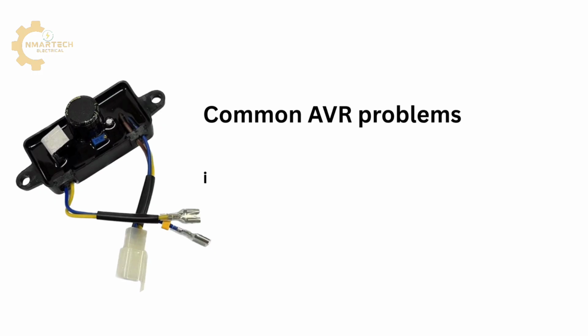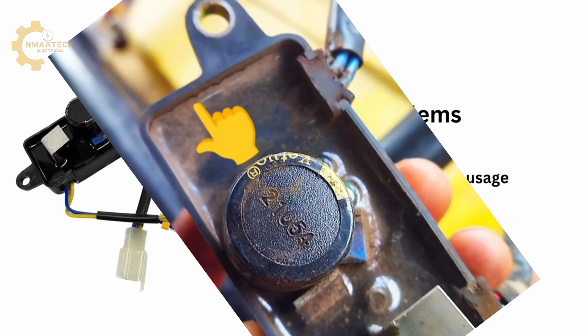Number 1 is simple wear out. Due to usage, it can get old. And what we should do in this case is just a simple replacement. Some symptoms of a worn AVR include delivering excess voltage, very low voltage, or no voltage at all. Sometimes you can see visible physical deformation of the AVR, just like what you can see on the screen.